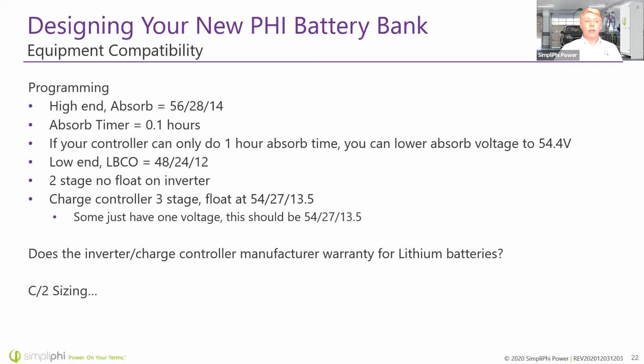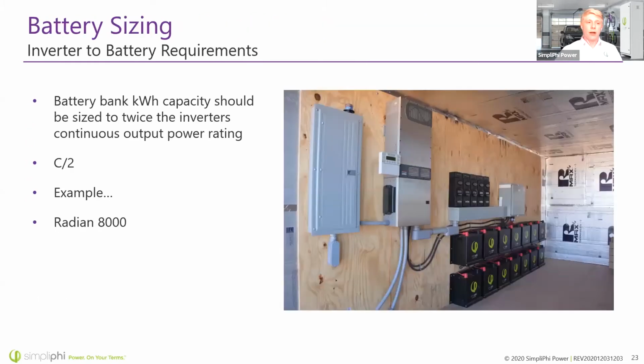Now, most importantly, make sure you follow the C/2 sizing rule. So I'm going to talk about that here. As far as sizing your battery system, the battery kilowatt hour capacity needs to be double the inverter's continuous output rating. So for an example, let's say you have the Radian 8 kilowatt continuous inverter. In that case, you need 16 kilowatt hours of battery storage. Simple as that. 5 batteries is over 16 kilowatt hours of storage, so 5 batteries per Radian is perfect.